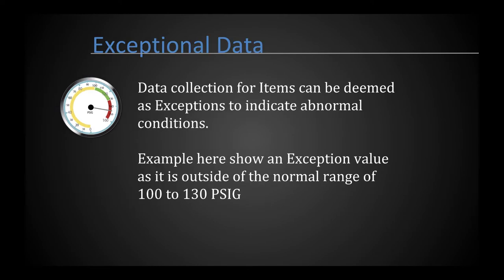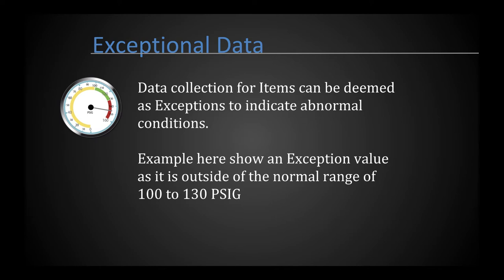When it comes to items or data points, you can specify the normal boundaries for each one. For example, a pressure gauge reading outside the normal range is called an exception — indicated when the needle is in the red area. During administration setup you specify normal ranges for numeric readings and indicate which status or selection-type readings are considered abnormal. Operators receive immediate feedback when equipment is outside normal operating boundaries. The color red is always reserved for exceptions throughout the software.